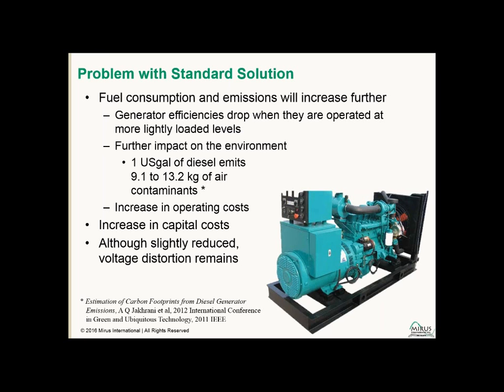Also, if we're doubling or more the size of the generator, of course we're going to have much higher capital costs. And even though a larger generator will introduce slightly lower relative impedance to the load, there's typically still enough impedance that the resultant current harmonics passing through that impedance are still going to create voltage distortion levels.